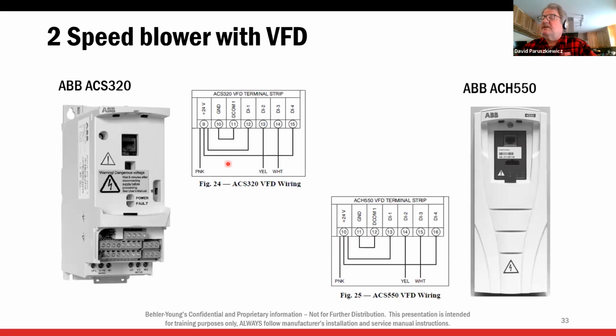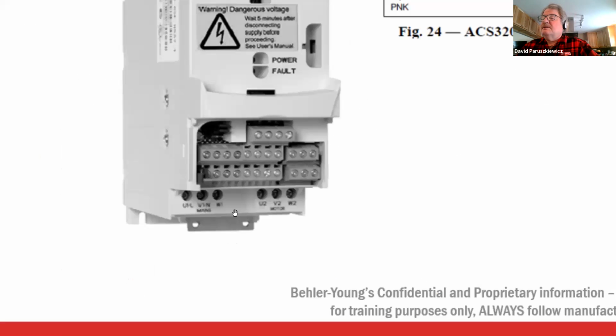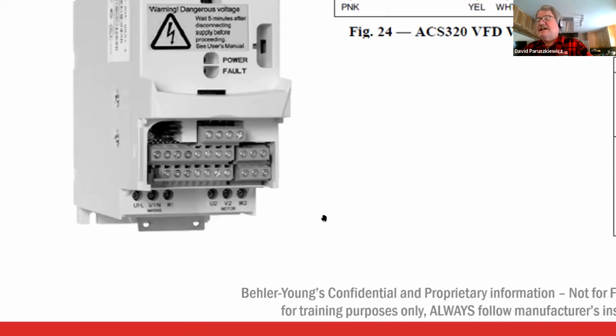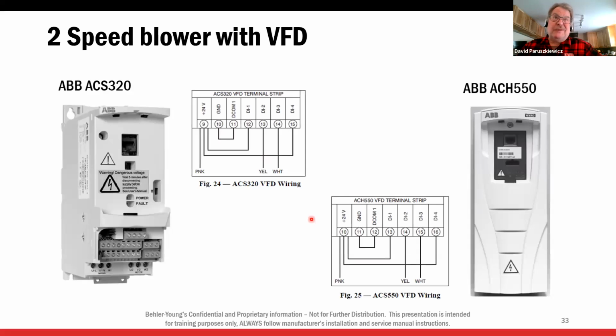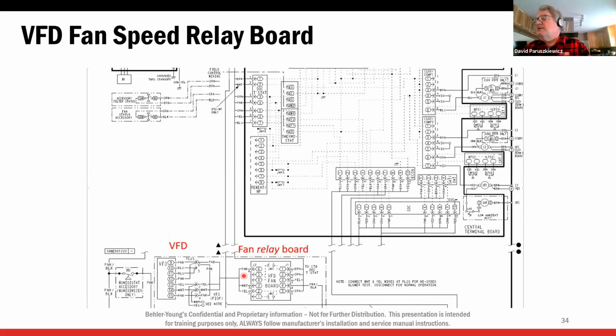So let's go back to this for a second here. So the input to the VFD down here, that's line voltage, L1, L2, L3. And then it goes through the drive, and when it calls for motor, it's going to send L1, L2, L3 out to the motor. Okay, that is an AC voltage coming out technically. We're changing the hertz. So I can check to see if I have output to the motor. It might not be a full 230. It might be 190. It depends on what the drive's going to do, but do I have power going to the motor? Okay.